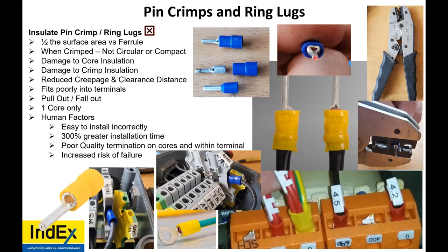The individual strands are no longer circular and compact. It is misshapen. There is not a clear means of crimping it where it is 4-sided or 6-sided. It is a misshapen mess. It also fits poorly into terminals. We have evidence of that. Also, you can only use one core, not 4, like this one, like they did. This is my installation picture from a few years back, one that I was inspecting.